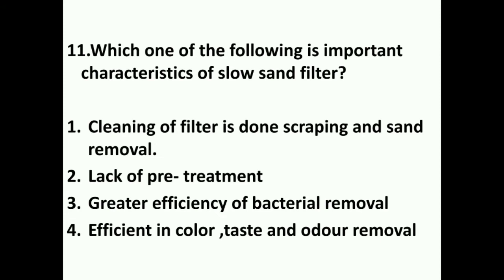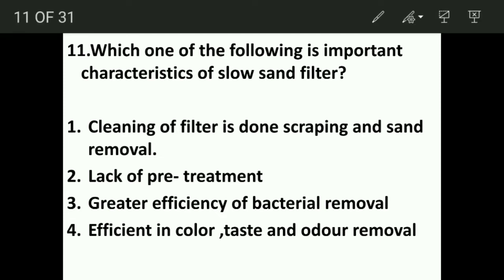Which of the following is a characteristic of the slow sand filter? The cleaning of the filter is done by scraping and sand removal — that is the correct answer. In rapid sand filters, coagulation is used as pre-treatment, and cleaning is done by backwashing. Slow sand filters achieve 98–99% bacteria removal. Options 1, 2, and 3 are correct characteristics.